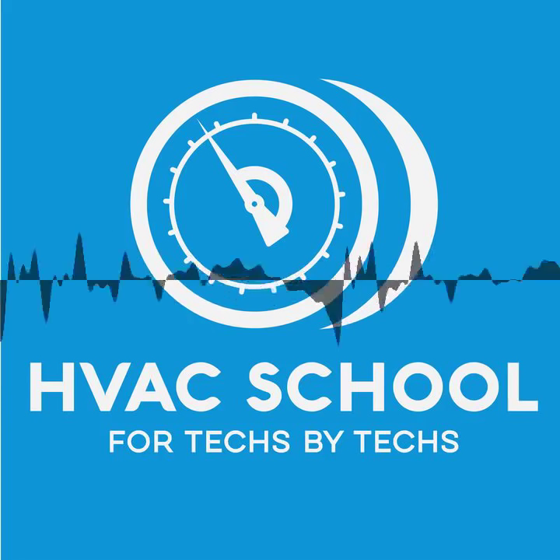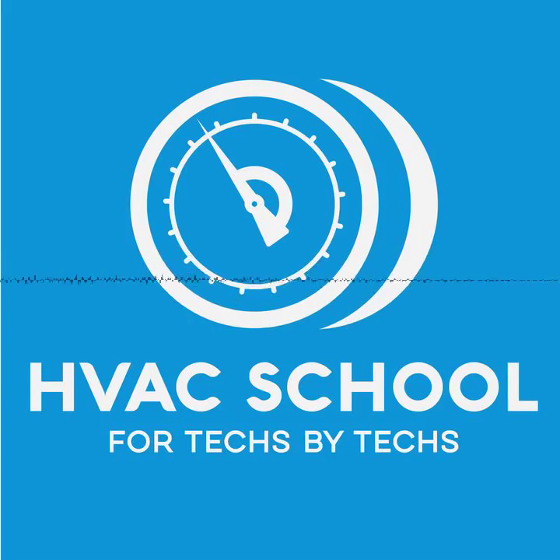All right, so let's talk about some common temperature measurement mistakes. I'm going to talk about one of the more common ones, and I was actually just talking to my service manager about this, and he gave a really good example. He was testing a system. He checked the superheat and subcool and the pressures and everything, and it all checked out to spec, and the customer's complaining that it just wasn't keeping up. 78 degrees in the house, equipment running. He was starting to think, okay, it's just not quite meeting the expectations of the customer, but it's running fine.